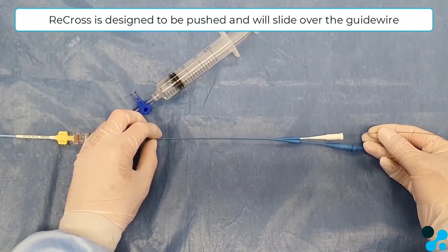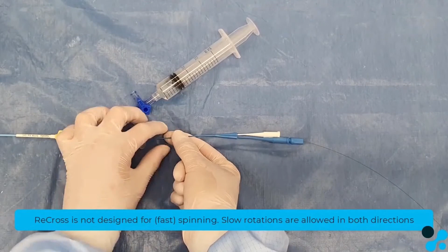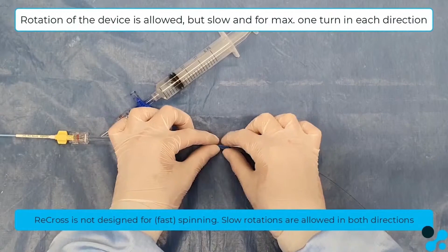Recross is a device that should be pushed over the guide wire, so it will slide over the guide wire. Its shape is not allowing fast spinning. Slow rotations are allowed in both directions, but if the torque tension is increased too much, it is important to stop because the forces will be too high. The recross is versatile and multifunctional.